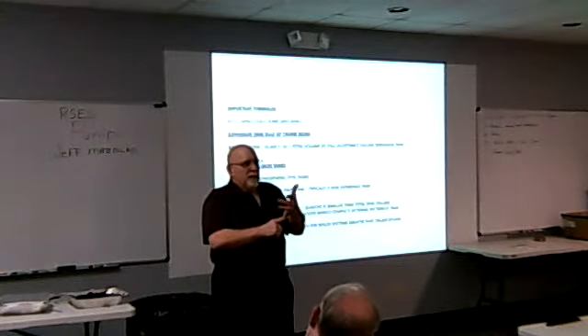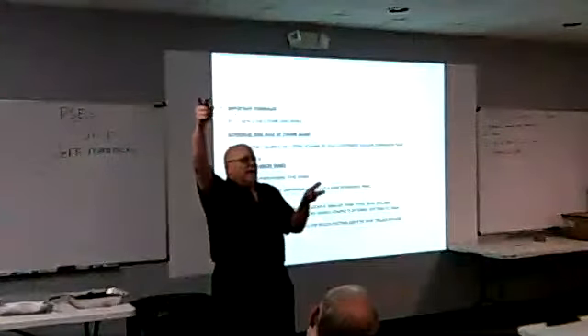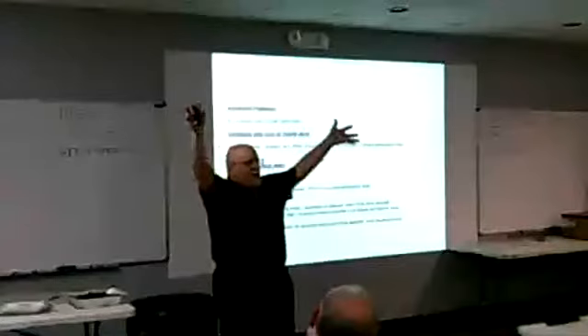So if you ever get a relief valve pop, first thing to look at is the expansion tank. Look at my filter. Did somebody screw with that? No, that's still good. Plain steel tank: look at the sight glass. If it's full, isolate the tank, dump it, realign it, you're good. Bladder type tank.